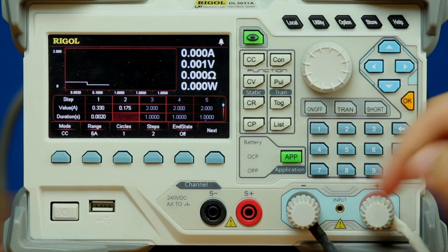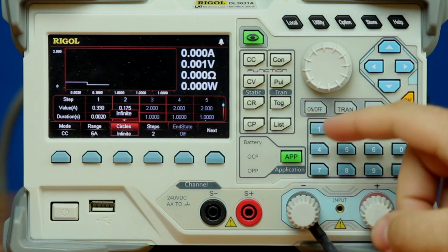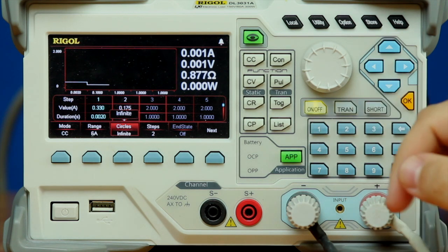And now that I've done this, I'm going to set our number of cycles to be infinite. And then in order to turn this on, I just have to press the on button here, and then to trigger it, I use the transient button.